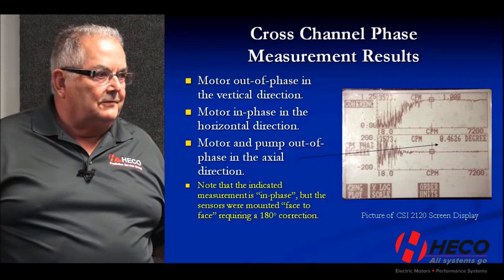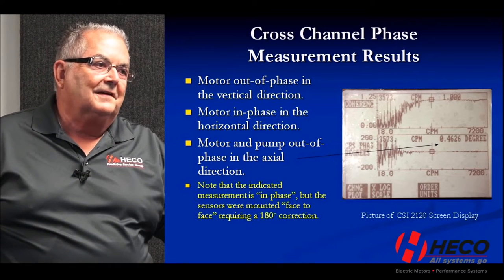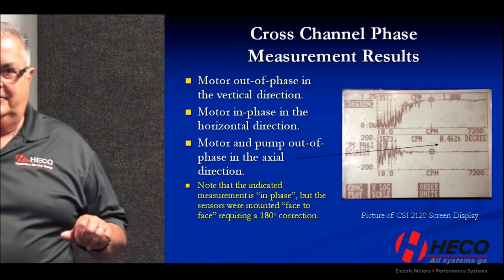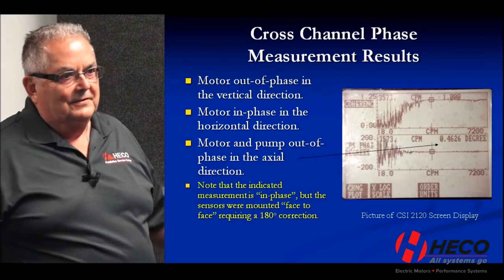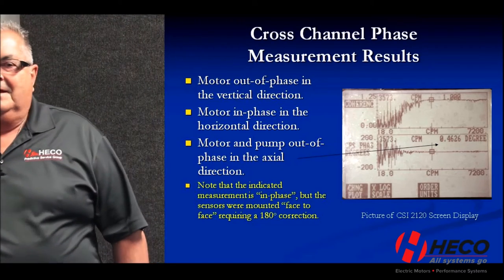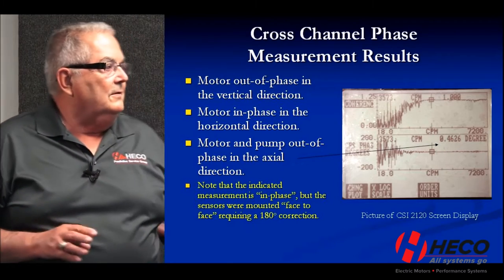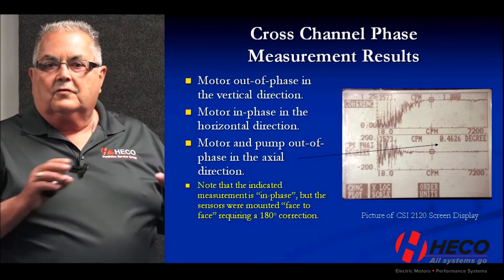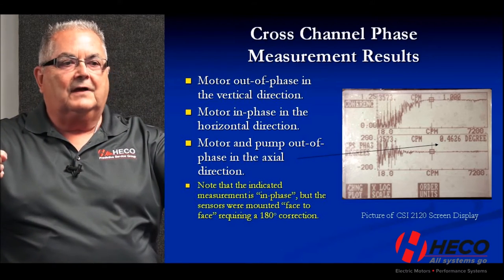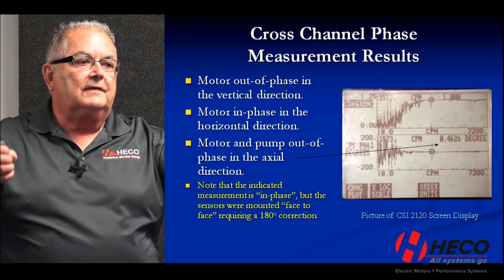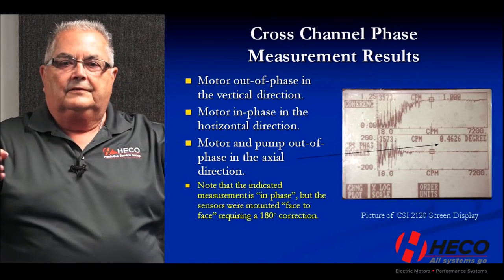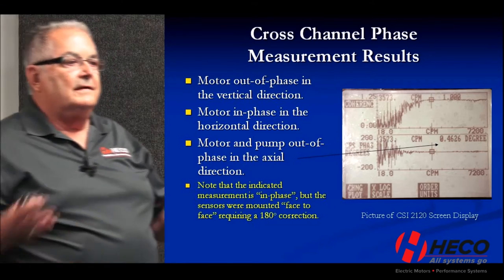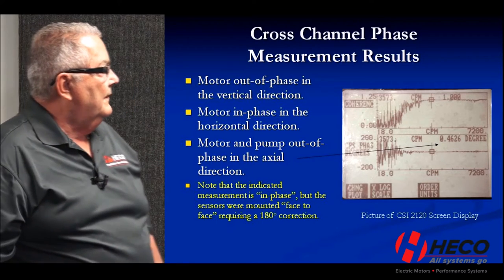So we said let's measure the phase angle. Many of you may be used to getting phase measurements by putting a piece of tape on the shaft and using a photo tach, but at 3,600 RPM that's not practical, and OSHA gets a little upset about that. Instead, we used a two-channel vibration analyzer to get what's called cross-channel phase — putting two sensors on at the same time and measuring the phase reference between them to see if they're in phase or out of phase.